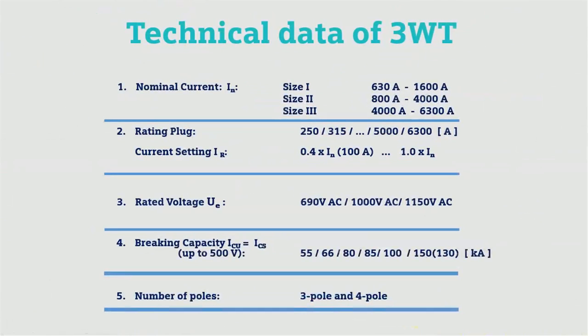These are the technical data for the Siemens 3WT ACB. The nominal current capacity ranges from 630 amperes to 6300 amperes in different sizes. The rating plug is from 250 amperes to 6300 amperes. Rated voltage, breaking capacity, and number of poles are given as per different sizes and makes.